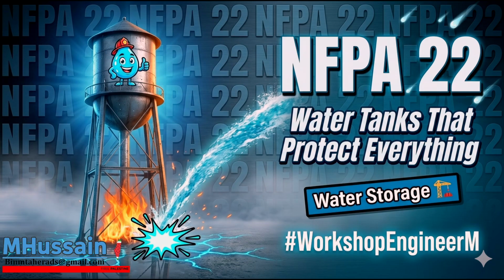The standard is extremely rigorous regarding their design because you aren't just holding static water. You're holding a mathematically calculated ratio of air to water. Exactly, and you're compressing it under significant pressure. It's essentially a loaded mechanical spring. The mechanism reminds me of a heavy-duty industrial-scale super soaker. That is exactly what it is.